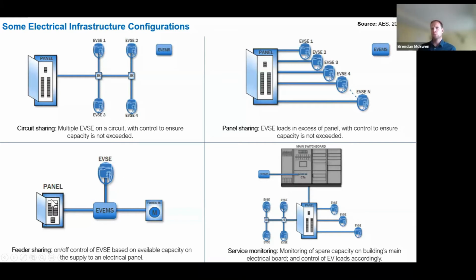There are also systems where this wouldn't happen on the feed to the panel, but actually on a branch circuit, where you'd be monitoring the feed to the panel and then adjusting the EVSE, which comes off of a branch circuit, or even sharing on a branch circuit between, let's say, a dryer and an EV. So you can have one of those two loads on, but not both. And since we usually don't have our clothes dryers running all night long, that provides perfectly adequate charging for the EV. So that's a range of technologies demonstrating feeder sharing that can work in single family homes or townhouse applications, especially, or sometimes small apartments.